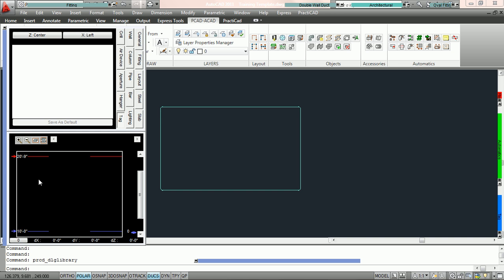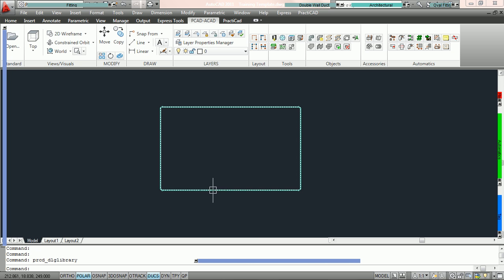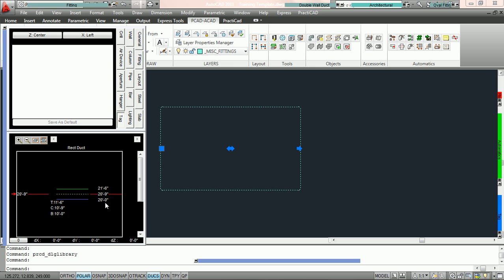And what we're going to do here is take a look at the elevation box and notice that we had created a reference point at 10 foot and set it to relative bottom. And we had created a mark with the name 0. And that happens to be the default name of the first reference point you put on your drawing. Now this duct, if we click on it and go to the elevation box, you can see that the bottom of duct is at absolute 20 foot. And there is a property for that, and it's called bottom elevation. The property bottom elevation means the absolute value of the bottom of that duct.